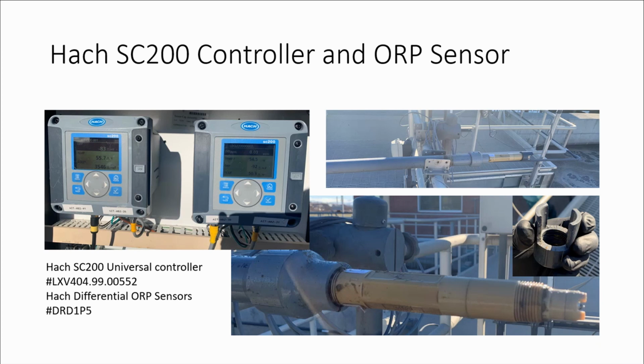It's a coupler. I think it was a 1.5 inch or 1.25 inch coupler, and we basically cut half of it out, but cut 2/4 out and left the other 2/4, and it protects the tip from being broken off. And we've never had another tip break since we've done that. And we'll go into that whole process of cleaning and calibration.